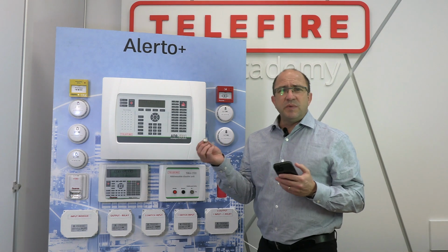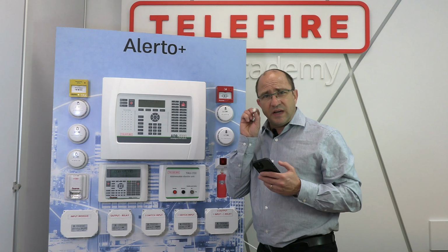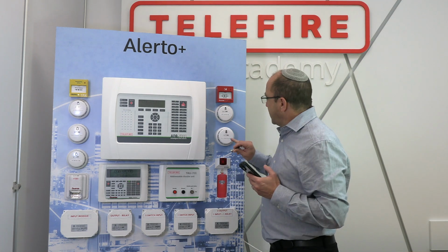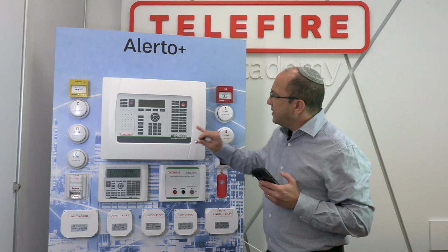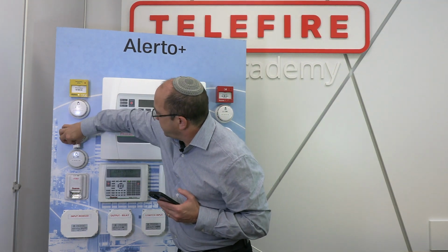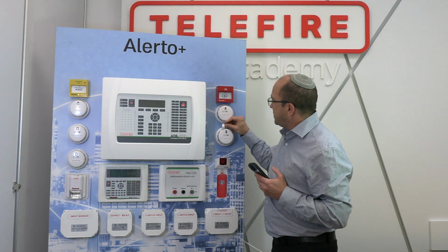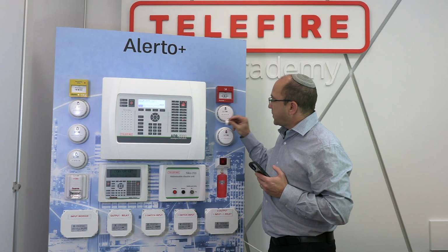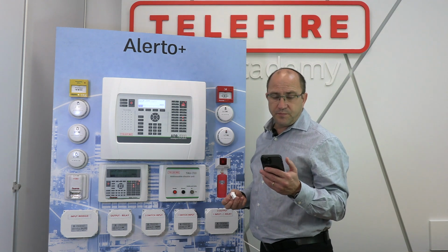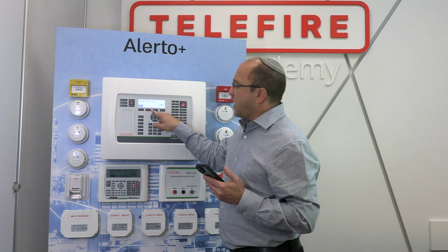Now I'm going to take a magnet because a magnet can activate an alarm on the detector. We have an activation with a magnet. Where the LED of the detector is, you just put it above. Let's say here, it's easier for me because I'm standing here. Now we have an alarm. Combined detector number 5 alarm.